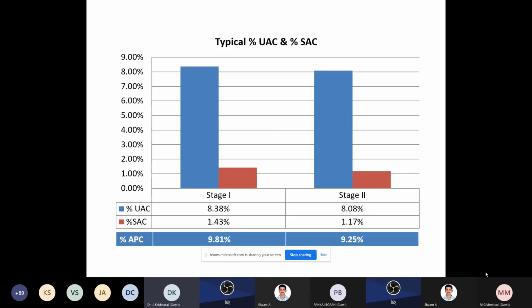Since auxiliary power consumption is related to the net heat rate of the unit and the plant, this is also one of the factors. If you reduce the auxiliary power consumption, then automatically the net heat rate will also be reduced. Typically, in thermal power station stage 1 units it is 9.81% auxiliary power consumption, and in stage 2 units 9.2%. Of that, 1.3% is basically coal handling systems and others, and 8% is all boiler and other auxiliaries. So these are the typical figures.